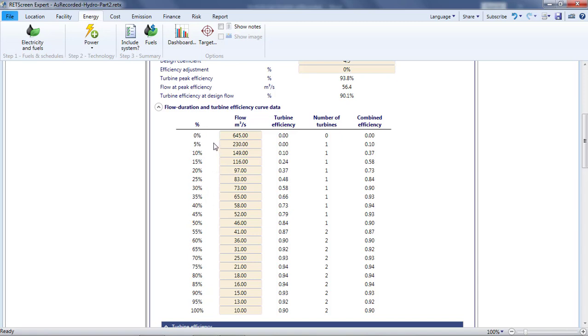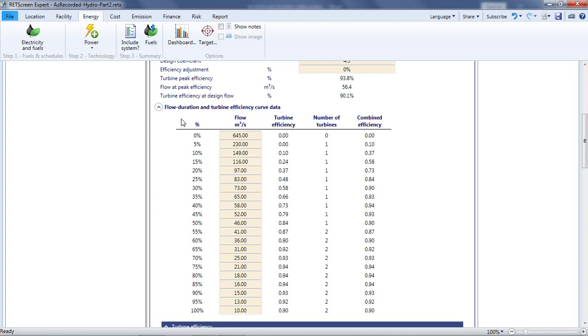The number of turbines column shows how many turbines are operating for flows varying between 0 and 100% of the project's design flow rate. This can be confusing. The percentages in the first column are interpreted in three distinct ways, depending on the column in the table. For the flow rate column, it is the percentage of the year that the flow rate is exceeded. For the turbine efficiency column, it is the percentage of the design flow rate for a single turbine. For the number of turbines and the combined efficiency columns, it is the percentage of the flow rate for the entire project.